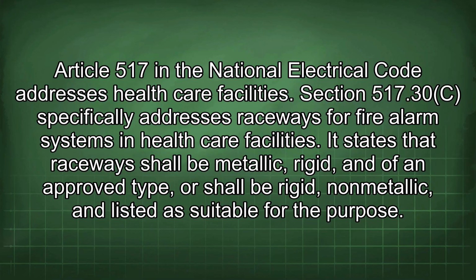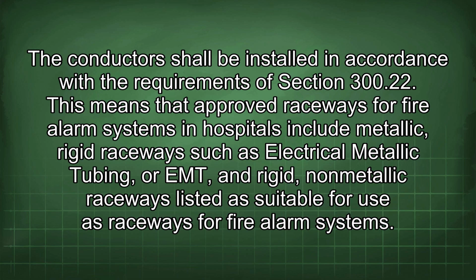Article 517 in the National Electrical Code addresses healthcare facilities. Section 517.30c specifically addresses raceways for fire alarm systems in healthcare facilities. It states that raceways shall be metallic, rigid, and of an approved type, or shall be rigid, non-metallic, and listed as suitable for the purpose. The conductors shall be installed in accordance with the requirements of Section 300.22.